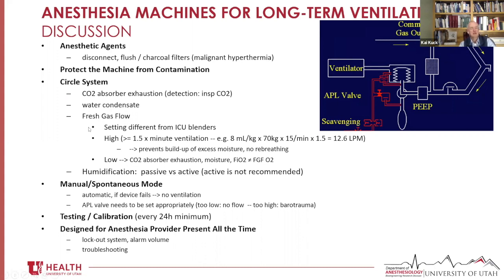The fresh gas flow in anesthesia machines, if you remember, you independently dial in the liters per minute of air and oxygen and maybe sometimes nitrous oxide. And then you have to calculate in your head what that oxygen concentration is for the patient. In the ICU, often you have blenders where you independently dial in a total of liters per minute and the inspiratory oxygen level you want. You don't have that here. ICU personnel need to think a little bit differently about it.